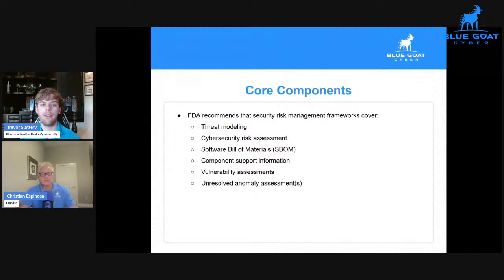What the FDA wants to see in a risk management report is essentially a snapshot of how all of these activities are performed, to make sure that they are performed up to relevant standards and up to relevant detail. So there is nothing slipping through the cracks. Nobody's forgetting to evaluate their SBOM. Nobody is forgetting to have a proper risk assessment framework and acceptability criteria in there. So it should cover all of these in a high-level summary and then reference out to the details of what is performed under each activity.